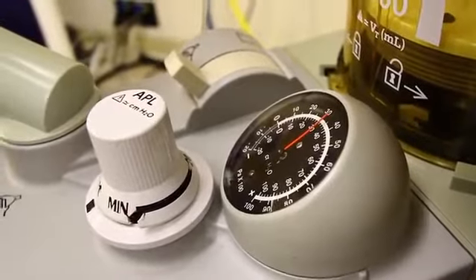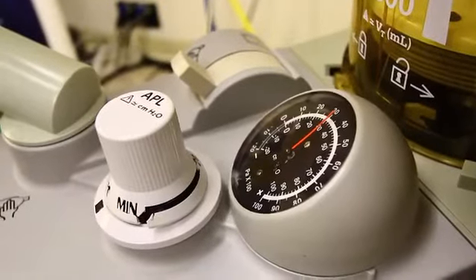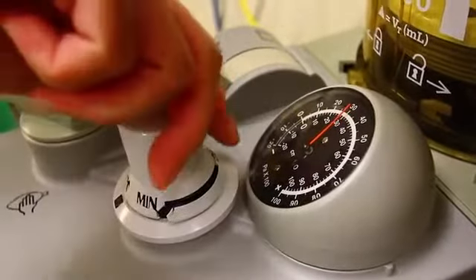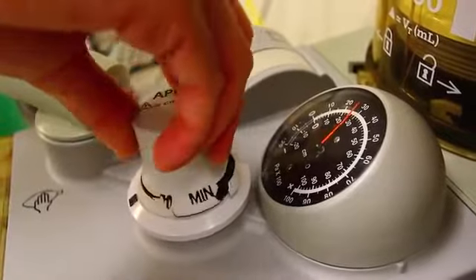With the system pressurized, verify that it remained pressurized for 10 seconds, then release the pressure by opening the APL pop-off valve.